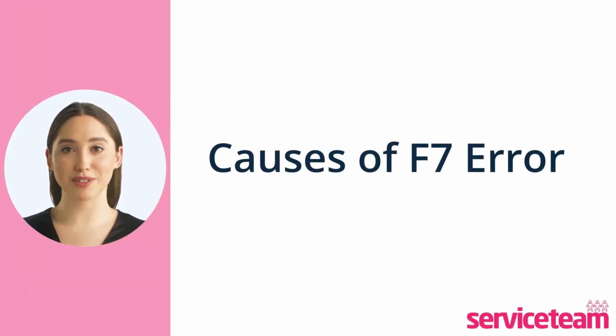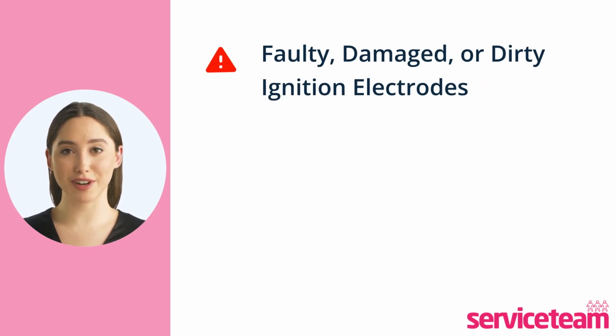Let's find out what causes the F7 error. Four main causes can trigger the F7 error code. The number 1 cause is a faulty, damaged or dirty ignition electrode. Boiler ignition electrodes are responsible for lighting up the fuel in your boiler. These electrodes get damaged or even clogged up with dirt over time. This can really mess up the boiler's ignition process, causing false flame detection.